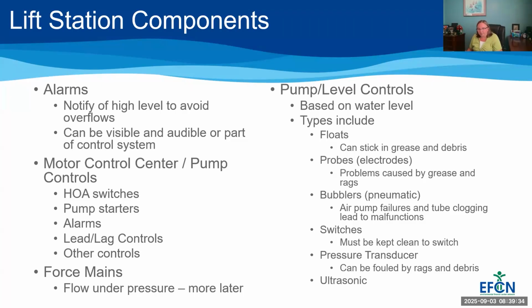Bubblers rely on an air pump, and if you have a fish tank aquarium, you probably have an air pump in it. You can kind of think of that kind of air pump to provide air so that the pressure can be measured as the bubbles are forced out of that tube. If the tube becomes clogged by rags or grease, or if the air pump fails, then the system stops working.